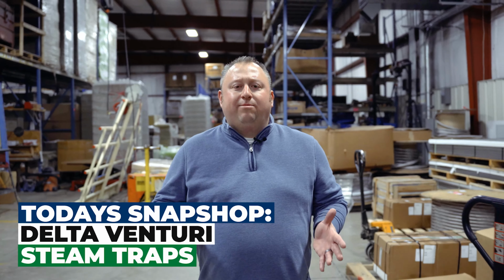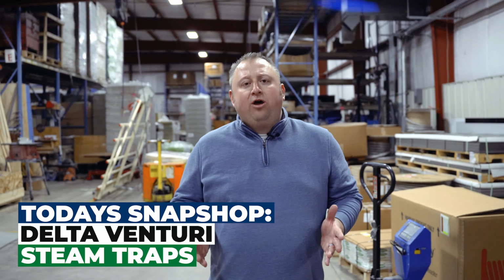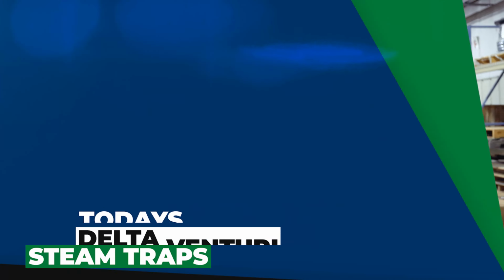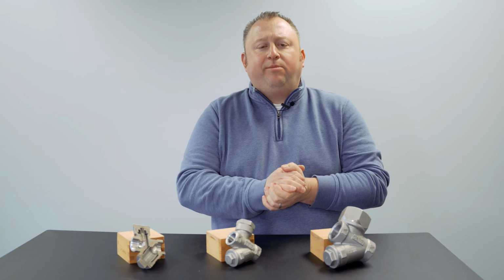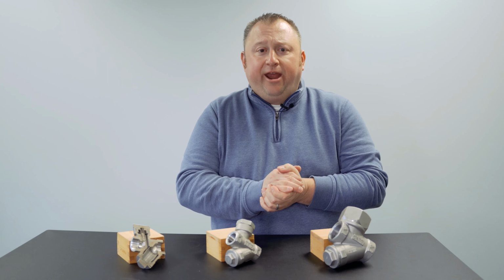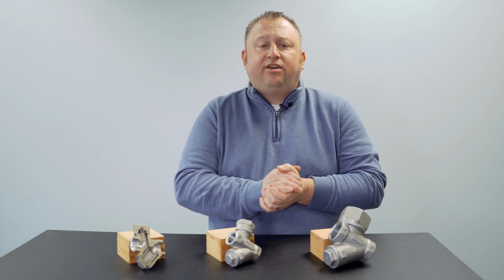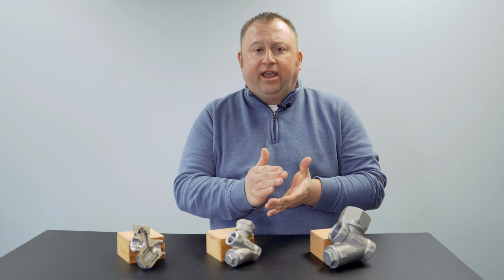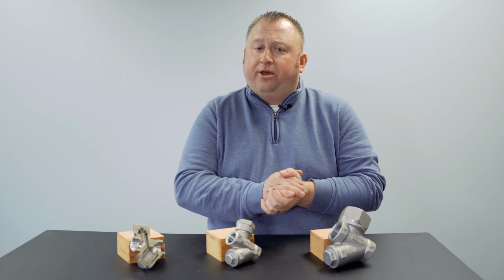Today, we want to give you a look at a Delta Venturi Steam Trap, an enduring component for a forward-thinking engineer. A steam trap is used in the steam process to not only vent air and non-condensable gas, but to continuously drain and release condensate while preventing the escape of steam from your system.